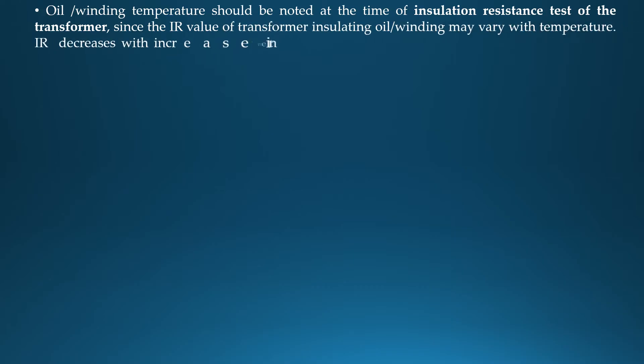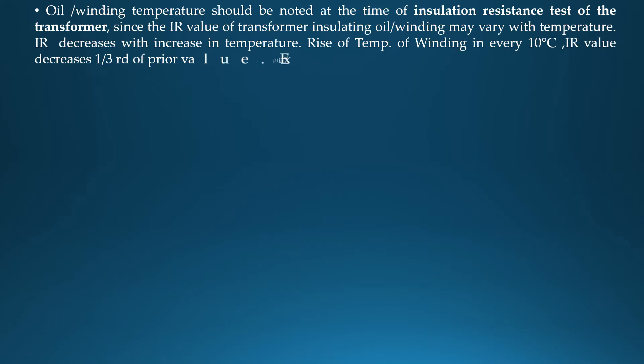Oil or winding temperature should be noted at the time of insulation resistance test of the transformer, since the IR value of transformer insulating oil or winding may vary with temperature. IR decreases with increase in temperature. A rise in winding temperature of every 10 degrees centigrade causes the IR value to decrease to one-third of the previous value.